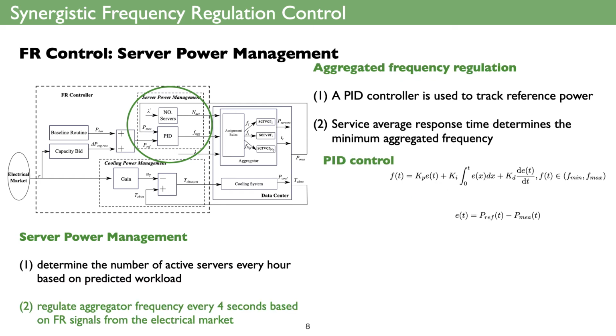The second function of server power management is to regulate the frequency at an interval of 4 seconds using a PID controller. The PID controller will output the frequency of the aggregator within the bound. The bound has a minimum value, the minimum frequency. It's determined by the response time required by the data center to provide normal computation service or web visiting service.